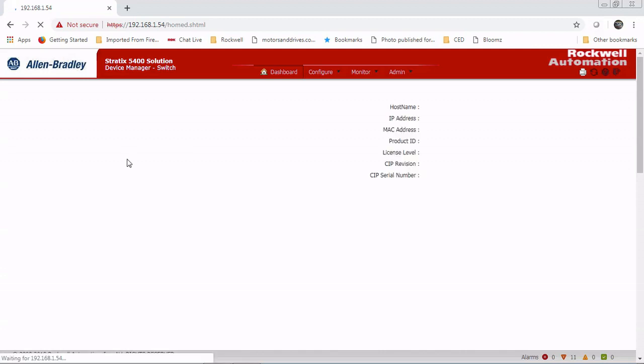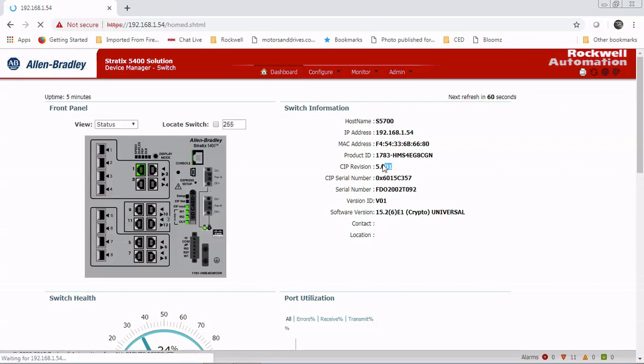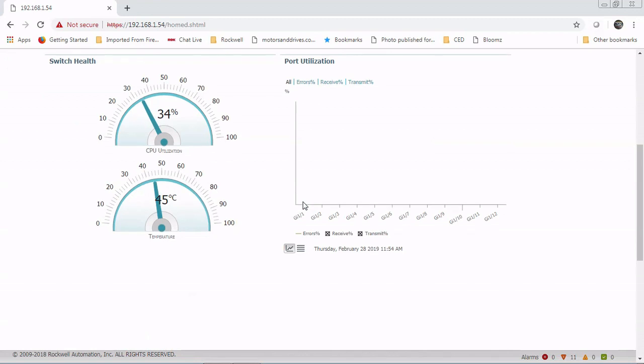It's going to log us in and take us to our dashboard for our switch. And that's when we know we're good. Right now we're talking to the switch, we're communicating. Once this all populates, you can see we have the MAC address, the firmware version, the CIP revision, which is what you would use in Logix. If you're adding this to the I/O tree, you would put this revision in.